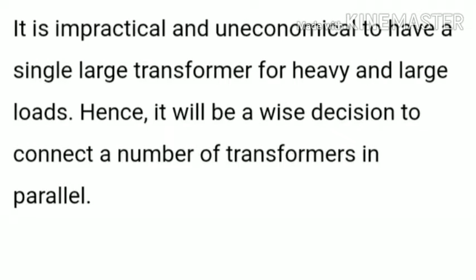So the second reason is if the transformers are connected in parallel, there will be scope for future expansion of a substation to supply a load beyond the capacity of the transformer already installed. So when transformers are connected in parallel, we can increase the future scope of expansion of a substation. So future expansion of a substation is the second reason for the parallel connection. So it is important for the purpose of parallel connections.